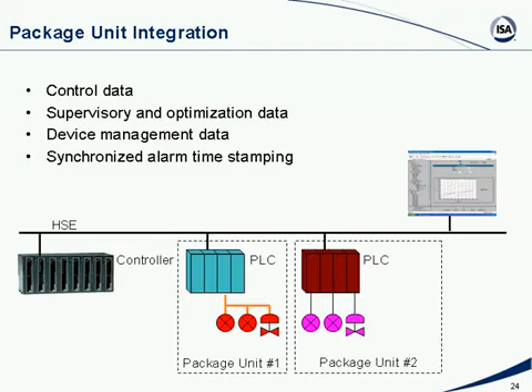That's still possible with Fieldbus. In fact, there is a Fieldbus interface module, or a gateway, between Foundation Fieldbus and Modbus. That's really the only gateway between Fieldbus and another protocol that I'm aware of. This Fieldbus interface module can mount on the package unit, and it can bring together the different Fieldbus devices on the package unit, creating the links to form the control loops, etc.